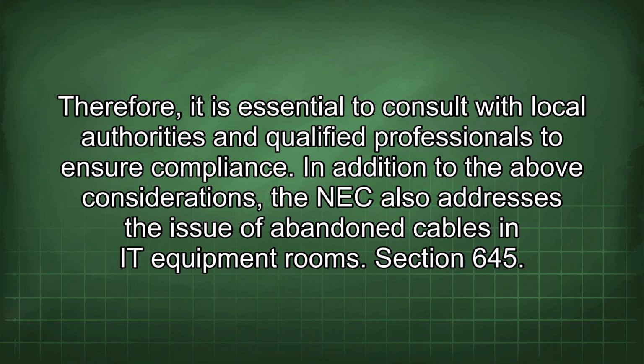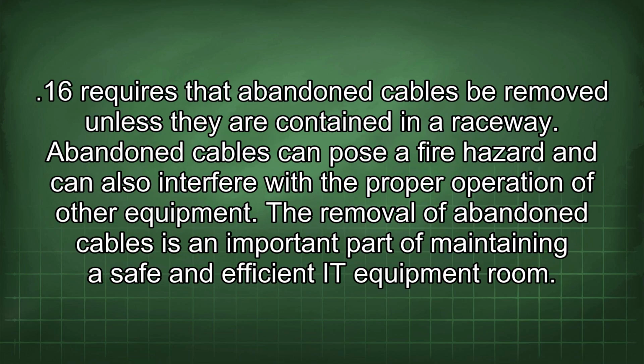In addition to the above considerations, the NEC also addresses the issue of abandoned cables in IT equipment rooms. Section 645(16) requires that abandoned cables be removed unless they are contained in a raceway. Abandoned cables can pose a fire hazard and can also interfere with the proper operation of other equipment. The removal of abandoned cables is an important part of maintaining a safe and efficient IT equipment room.